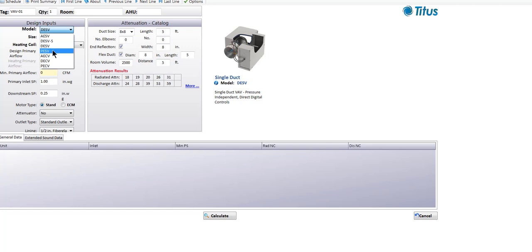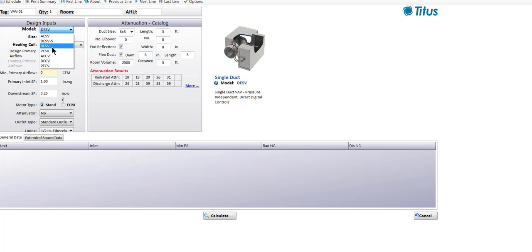You probably don't see too many projects these days with pneumatic controls — maybe if somebody's finishing out a floor of an old hospital or government building. Analog electronic controls are a niche product where you want to add a few zones of control without tying into a building automation system. But for large projects, most people are going to want the DESV with digital control and all the reporting and monitoring capability that comes with it.